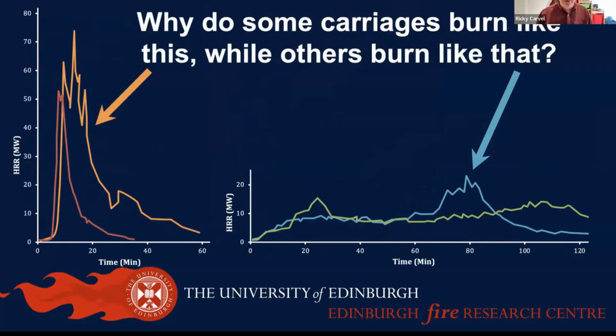So some of them have a short period of growth, a couple of minutes, then appear to have very rapid fire growth to a high heat release rate. Those graphs on the left-hand side are going up to 50, 60, 70 megawatts of energy release within 10 minutes of ignition. That's actually insane. If you're used to dealing with fires in the built environment and buildings, you might be talking about things going to 3 megawatts in 10 minutes. No, we're going to 70 megawatts in 10 minutes - literally an order of magnitude bigger.